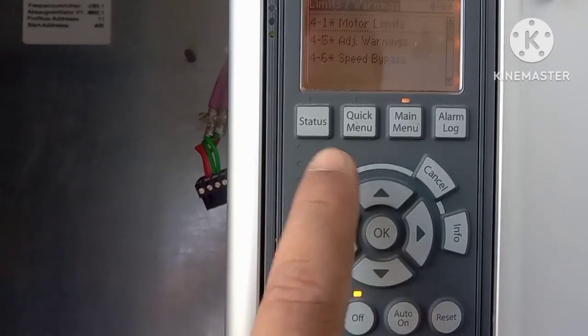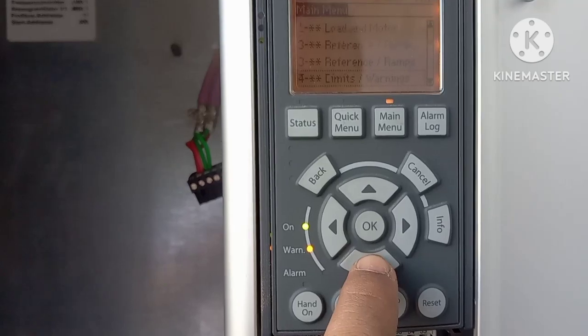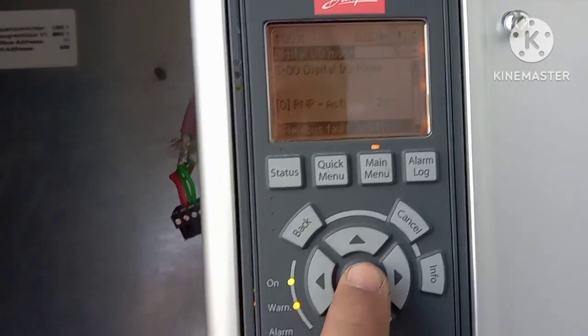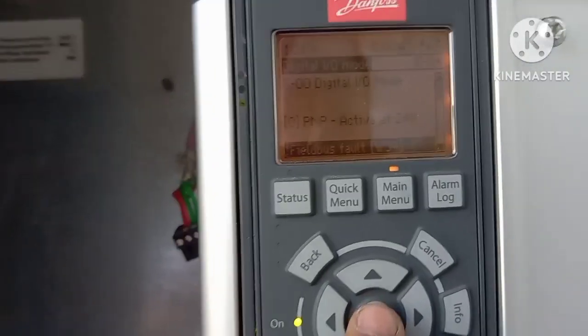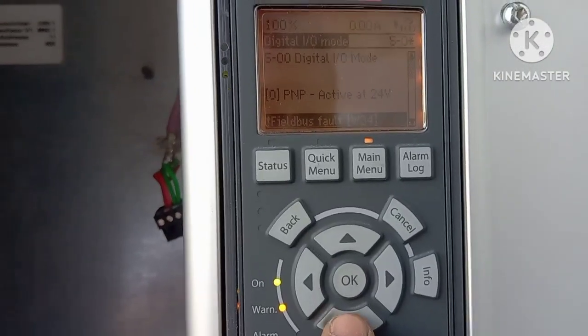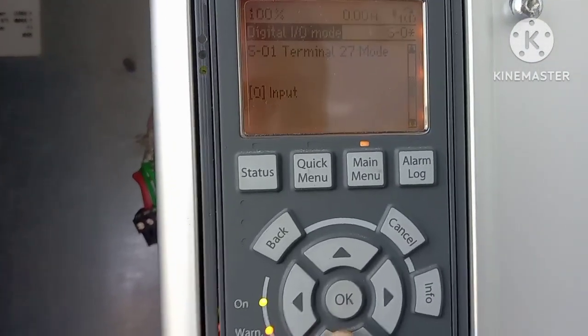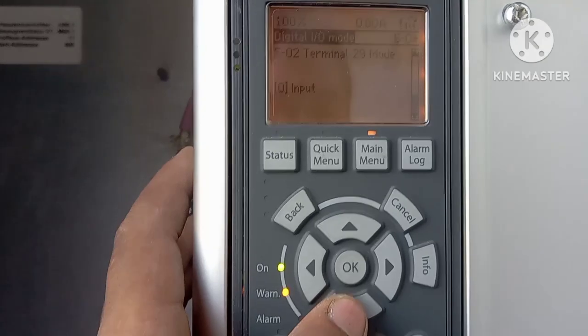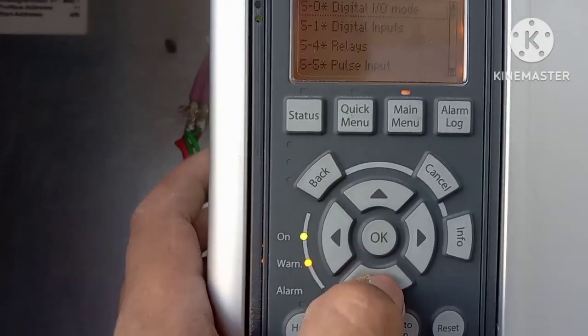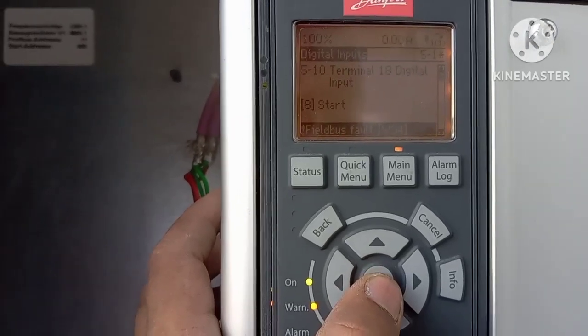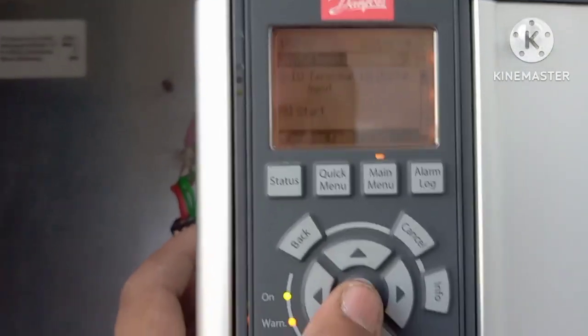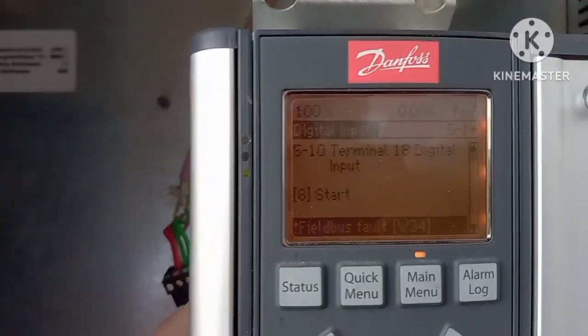Moving to Digital Input and Output — from here you can set your digital inputs and outputs. I am using PNP configuration. Terminal 27 mode is set to input. Terminal 29 you can set according to your requirement for digital input.